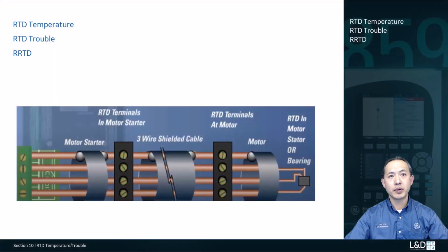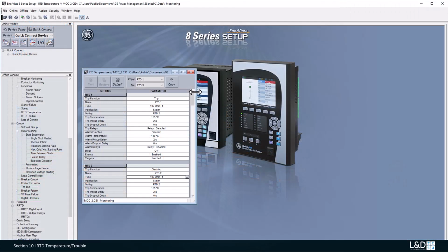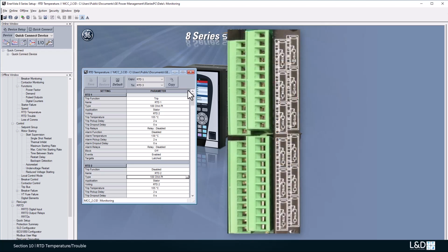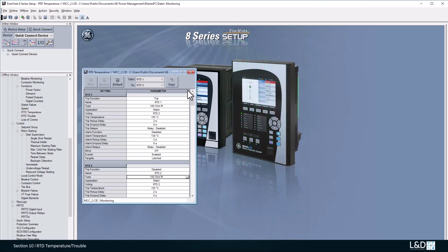The 859 relay can monitor up to 12 RTDs and 12 RRTDs. In this session, we're going to introduce the RTD temperature, RTD trouble, and RRTD, the remote RTDs. The 859 has I/O cards installed in the relay that can supply up to 12 RTDs. To enhance the accuracy of the RTDs, ensure all 3 cables are of the same length and gauge. In addition, the compensation and return wires must be connected to the RTD side and not on the relay side.